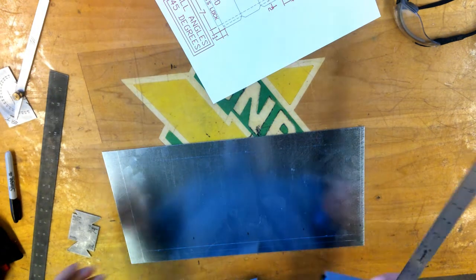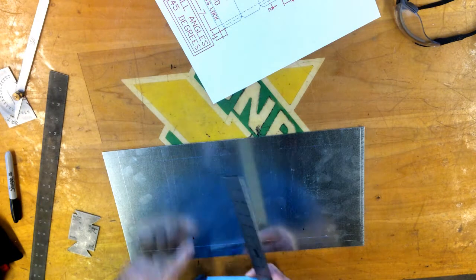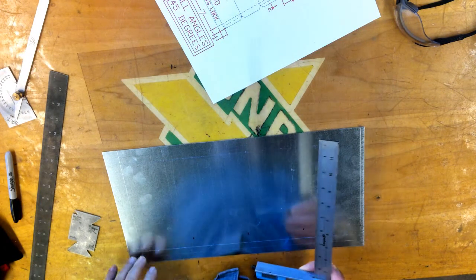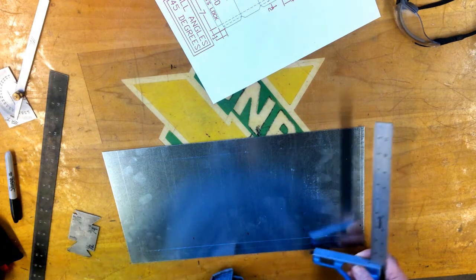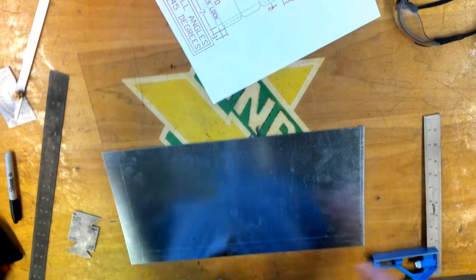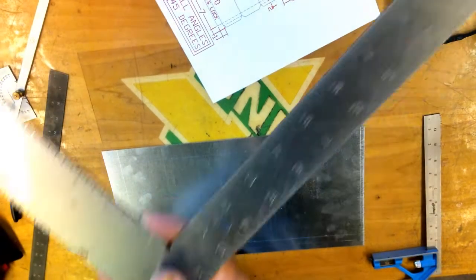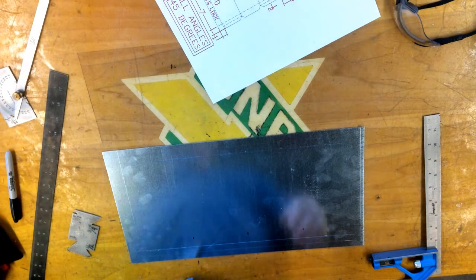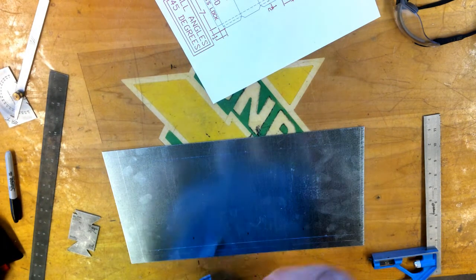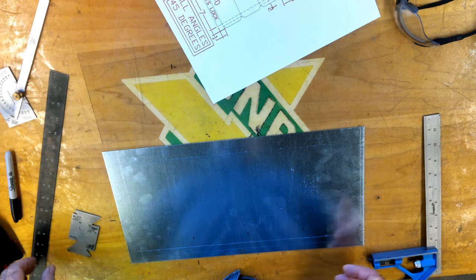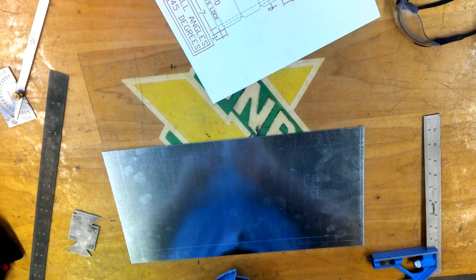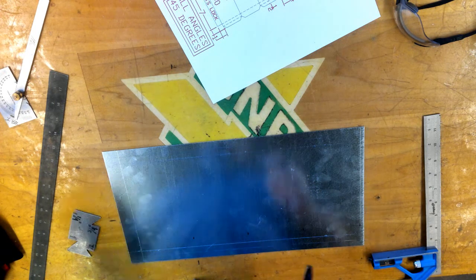So now using a combination square, I would mark my intersections for my bend lines at my 4-inch intervals. Depending on the size of my ductwork, I might have to use a framing square or a T-square, marking 2 points and connecting with a circumference rule or a 4-foot rule, whatever the case might be.